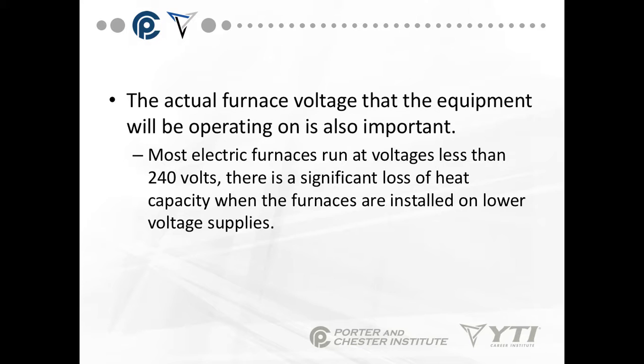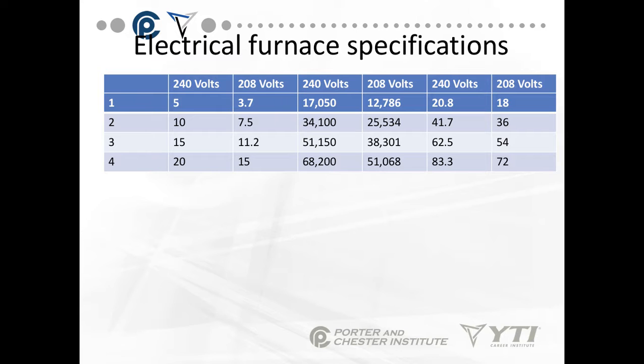The actual voltage that the furnace will be operating at is also important. Most electric furnaces run at voltages less than 240 volts. There's a significant loss of heat capacity when the furnaces are installed on lower voltage supplies. This is an example of an electric furnace specification. The kWs are rated on the second line of blue near the top. So we have 5 kW, 2 heat strips is 10 kW, 3 heat strips is 15 kW, and 4 heat strips is 20 kW. At 208 volts, each heat strip is 3.7 kW. And then it also gives you the BTU equivalents of that.